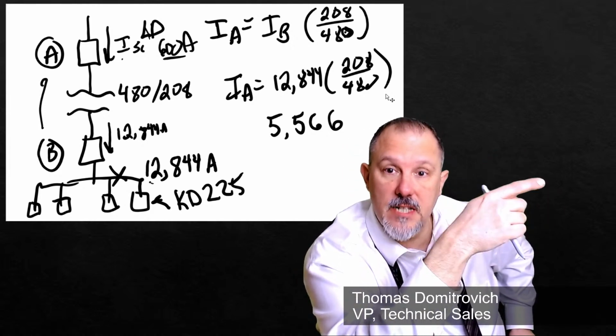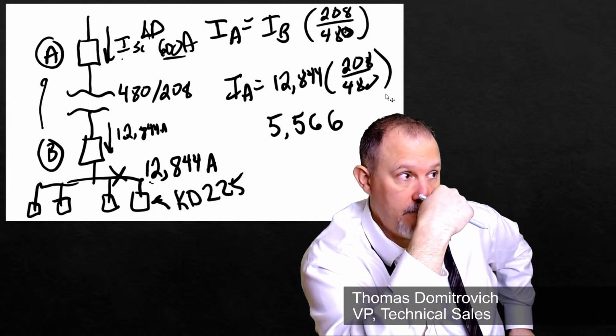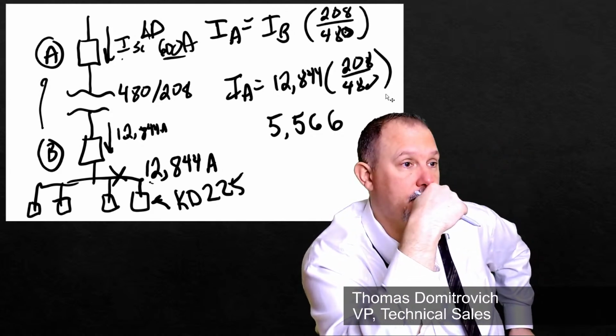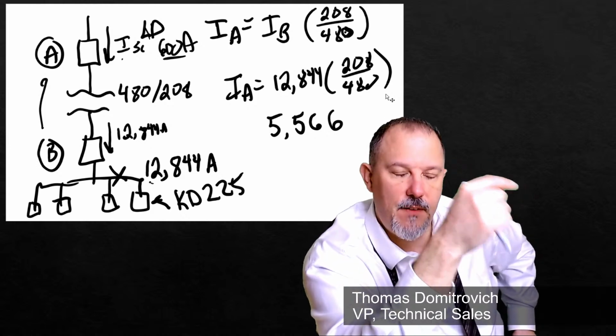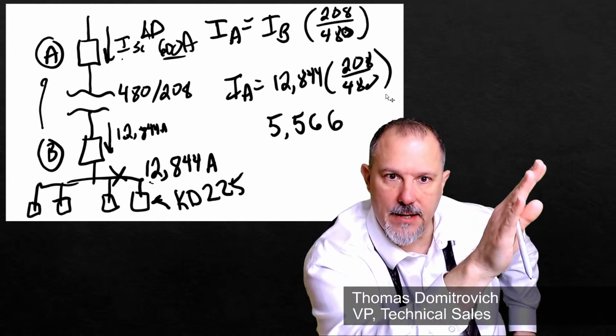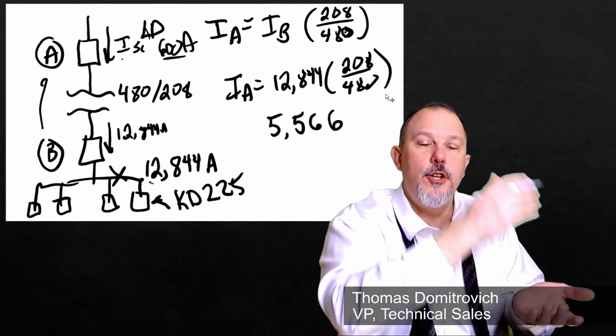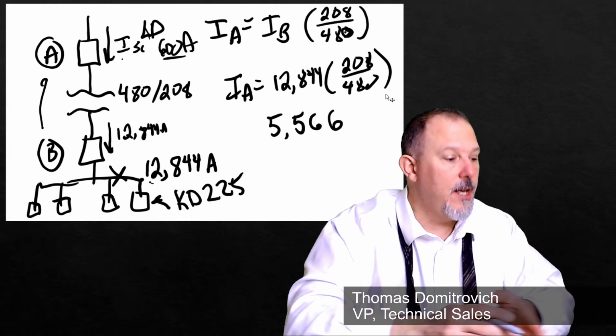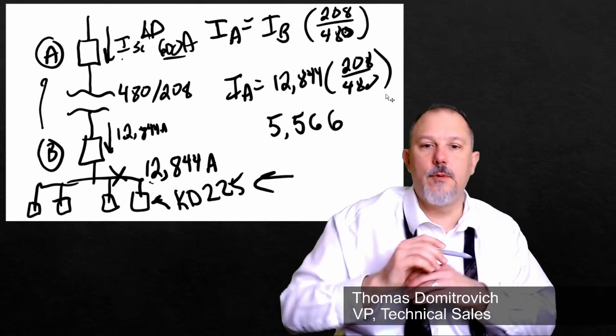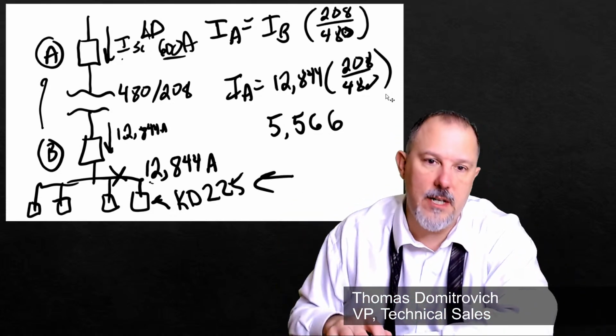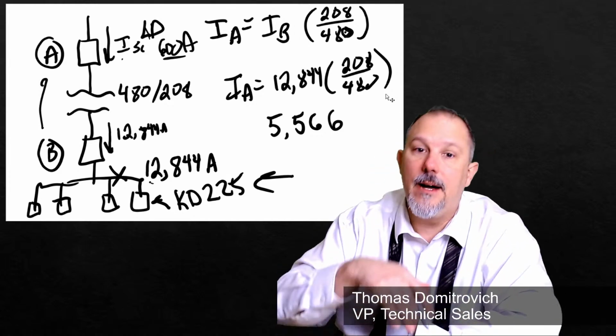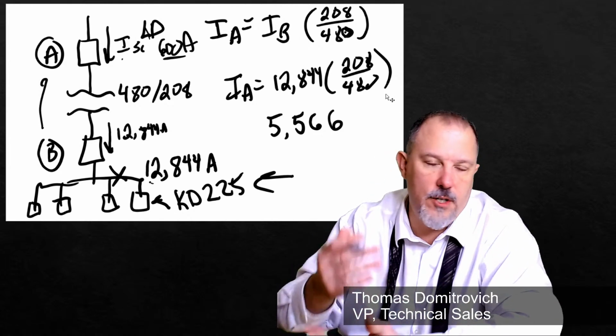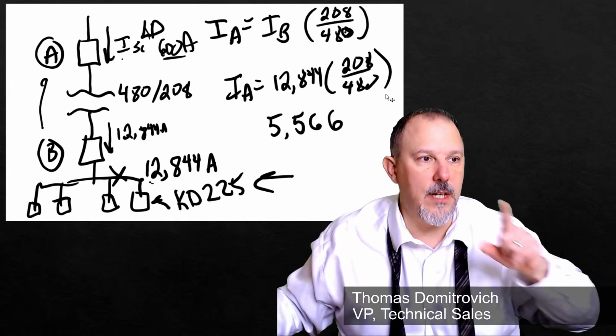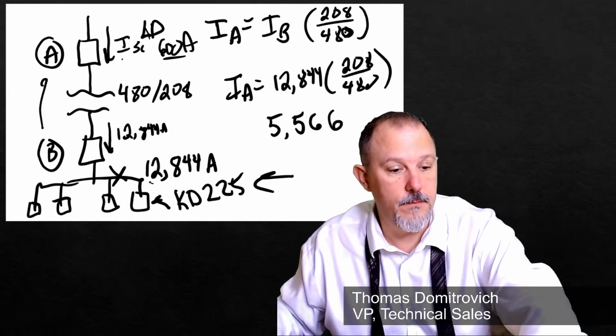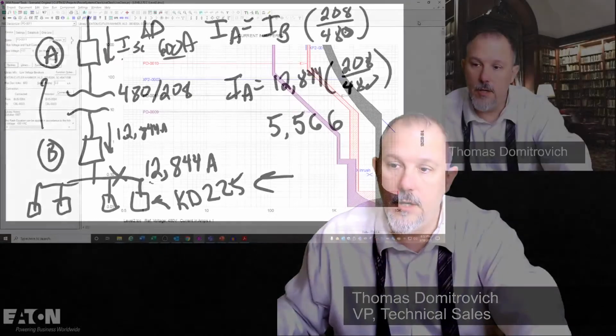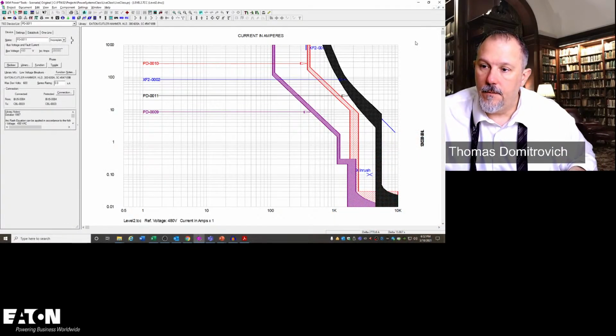So the 225 needs to be evaluated with that primary LD circuit breaker. And in this case, I know it works because I only have to selectively coordinate to 5,500 amps, and I'm good up to 10,000 amps. So that's how you go across a transformer. You don't have to worry about the two, and that's an exception in the code, but you do have to worry about these breakers down here, and you would use the fault current. Now, if you say I'm going to coordinate to the ground fault current, then you coordinate to the ground fault current, or the arcing fault current, whichever one you have to do, okay? And that is what gets you to your selective coordination, and you would do that all the way up through the system.